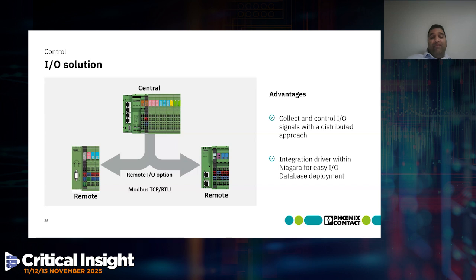But we don't stop there. Phoenix Contact have actually built a Niagara driver that allows for easy I/O data point deployment. What we mean by that is connecting all of the modules on your remote coupler. You can connect another 63 I/O modules on that remote coupler, whether it's TCP or RTU, it doesn't matter. The driver itself will automatically scan that coupler and tell you what connected modules you have on it.